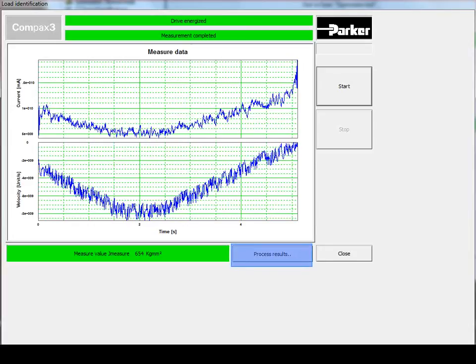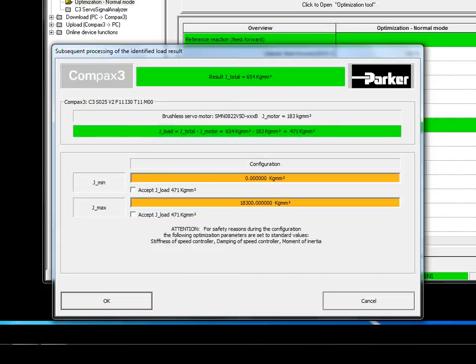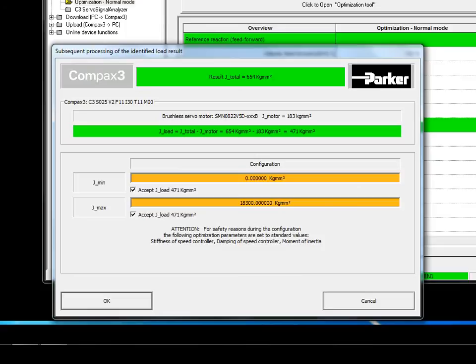On the bottom, if you click process results, you can see what it's calculated for the minimum and the maximum inertial values. If you go ahead and click that, that will then change the drive configuration, the inertial values that are in there. So it will scale the stiffness and the damping gains based on the inertial value instead of the unknown value of the zero as being the minimum and the very large number for the maximum. And now your rotary servo motor has been tuned.